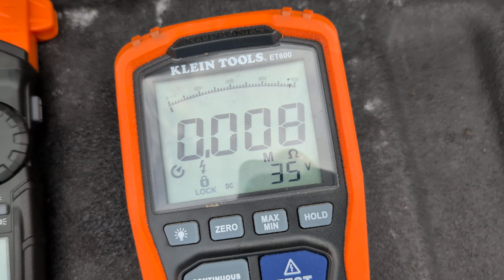When I actually measure this fixture that had a lot of water and it was faulted, I'm measuring open line, and that's because it's only applying like 3, maybe 9 volts, whatever the battery is in this thing. That's what it's applying to these probes to see how much current is going to flow, and it's not enough voltage to push through that fault that we know is there.